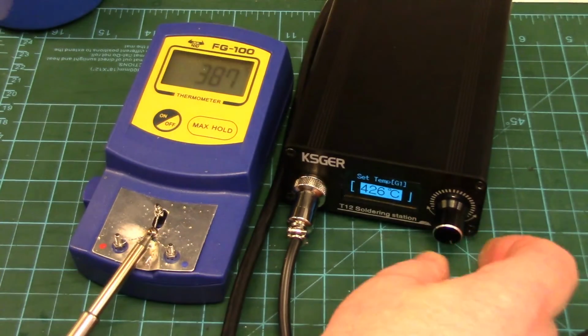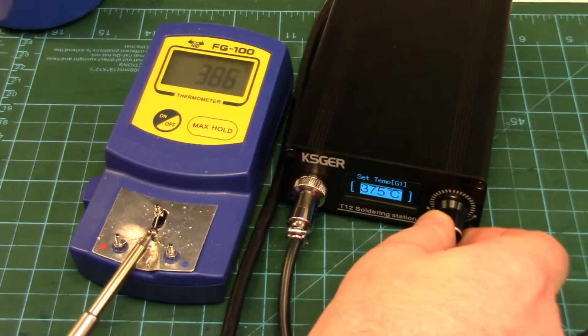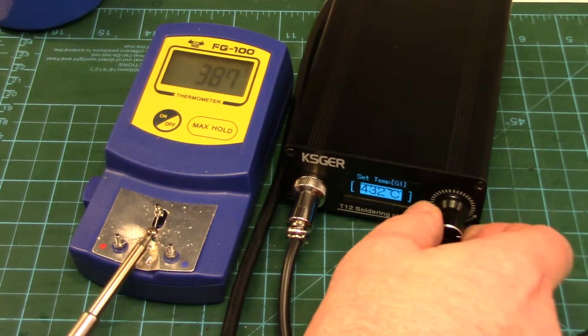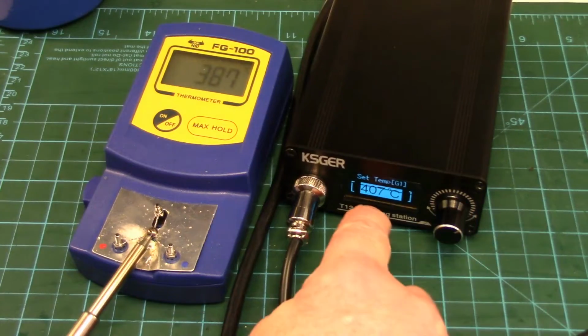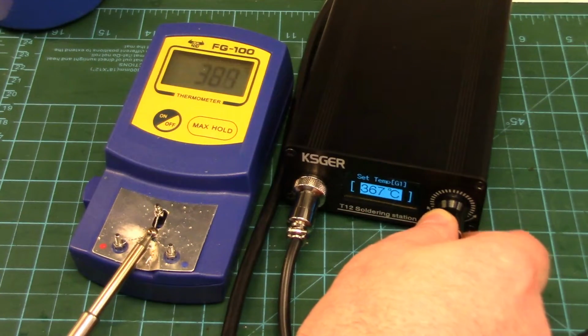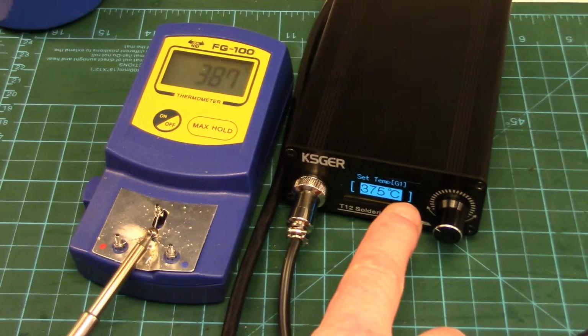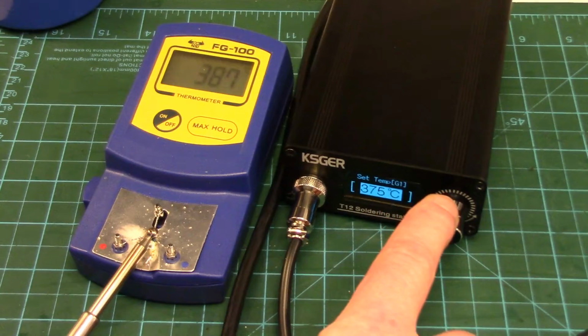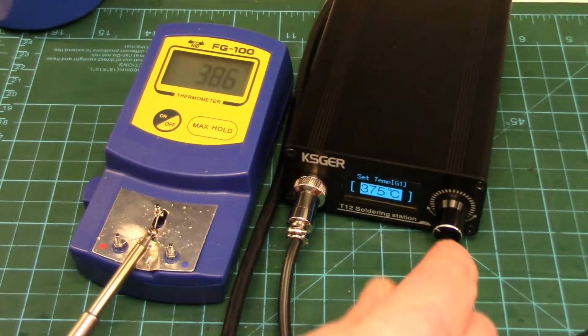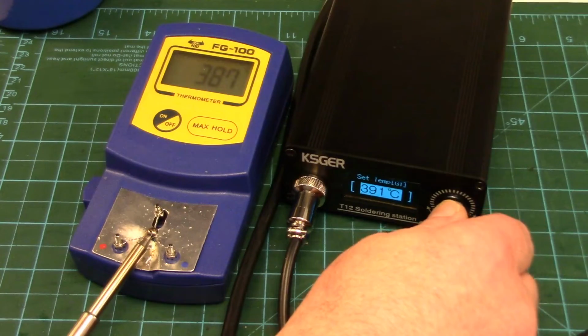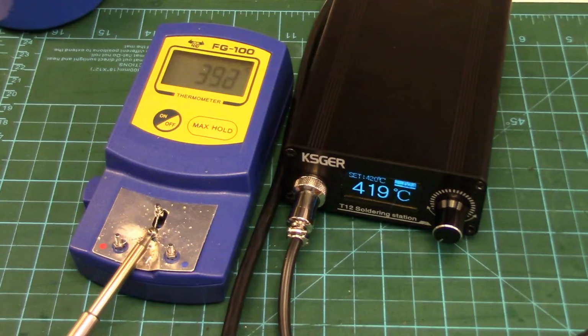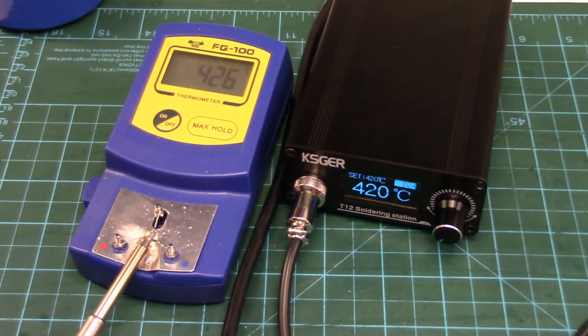You notice on this station, the encoder dials up and down. If you go slow, it changes by 1 degree increments; if you go fast, then it goes by 10 degree increments. It's hard to see. Whereas the old 2.1 version, you could set that in the programming. You could set what your incremental changes were, and I had it at 10 degree increments. You know, I don't need 1 degree resolution. As you saw there, it had stabilized around 384, so it wasn't bad at all. And there we go, boom. You can see how quick it comes up. So not bad without even doing a calibration yet on it. So that's the type of accuracy you can get.